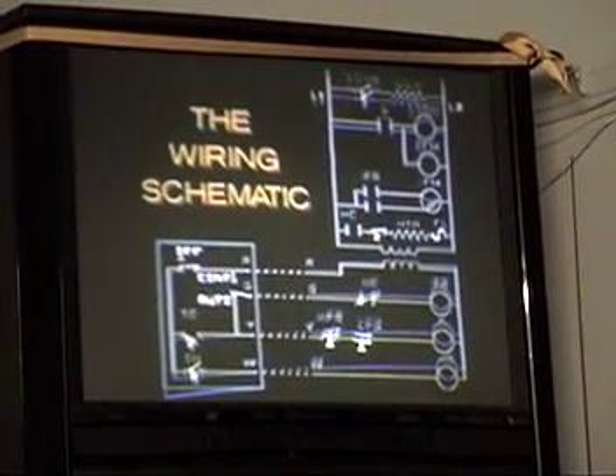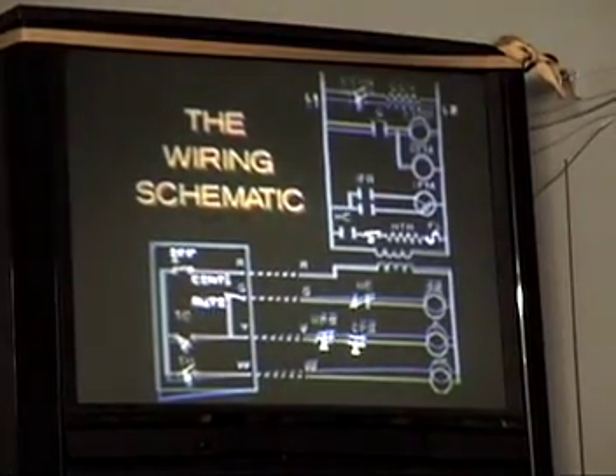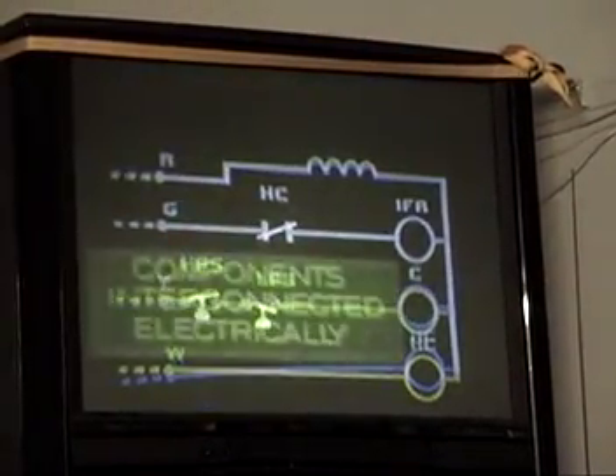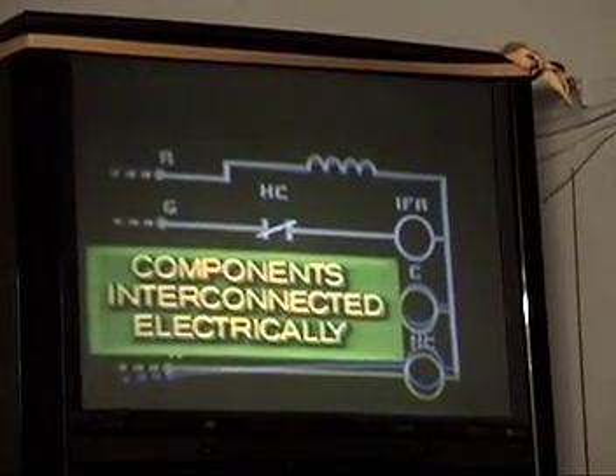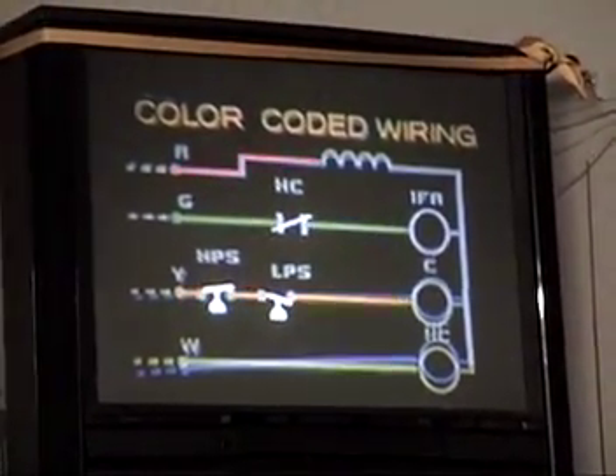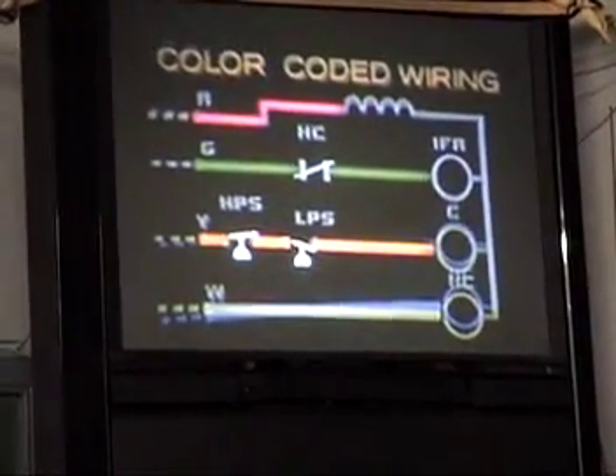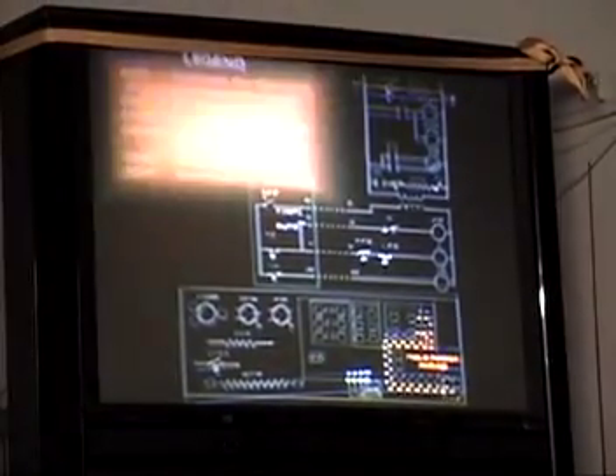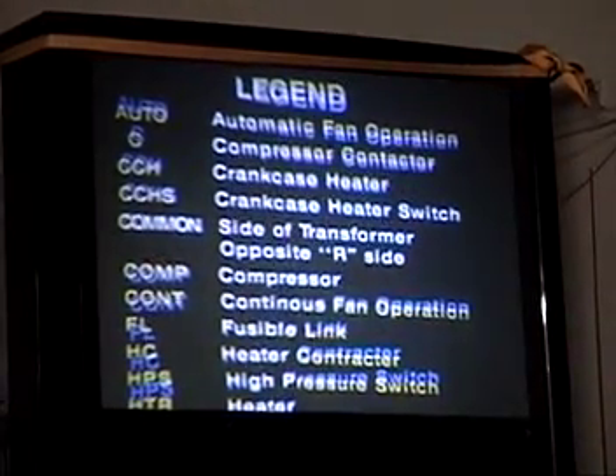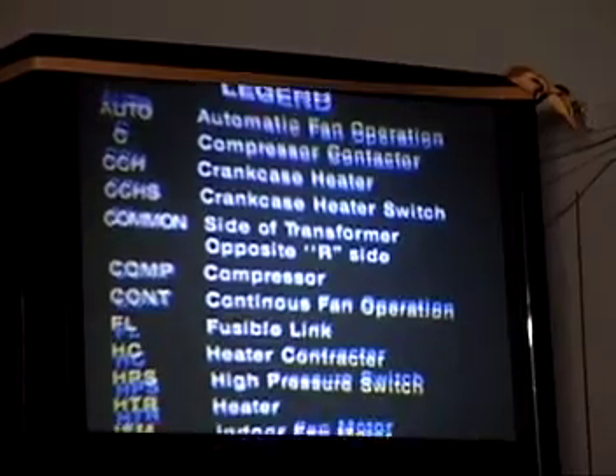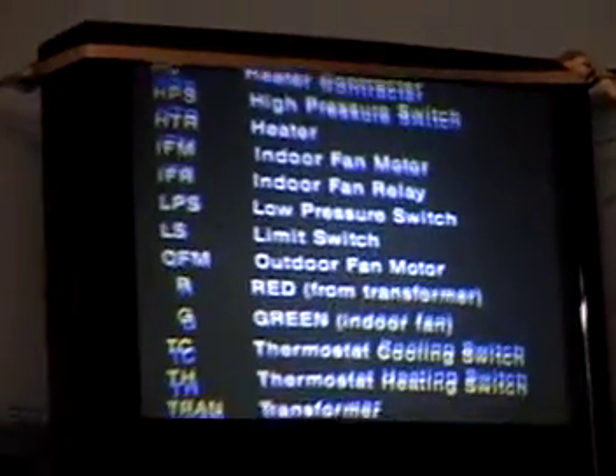The second section, the wiring schematic, shows the way the components and wiring are connected to produce an operating electrical system. Unlike the physical location section, it does not identify location, but shows how the components are interconnected electrically. Wiring is color-coded by many manufacturers to make it easier to identify particular wires in the unit. The third section, the legend and notes, further explains the components and provides additional special information. Note that the abbreviations as shown on the diagram are explained here. It's always important to read the notes first when looking at a wiring diagram, since they help to explain any unit particulars, such as time delays that are not easily shown in schematic format.